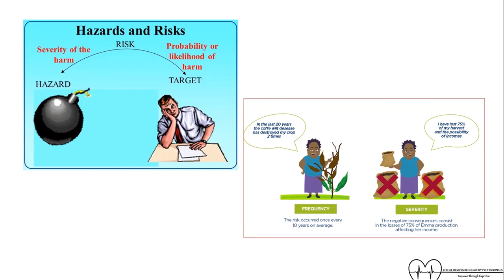I guess it's always, please think, first of all, start identifying, which I already touched upon, what is the hazard, what is the hazardous situation, meaning when it will happen. That is very, very important, and it's indirectly linked again to use, because you may identify in your FMEA that this failure mode is crazy, but it has hardly any risk to the patient because they don't use it this way. Then there is harm, and then you estimate, which is now the trickiest part, the probability of occurrence of this harm, then the severity of harm, and then multiply or combine them to estimate the risk. And below, what you see, green, blue, green, yellow, red, is a standard one which we get from ISO 14971 or as such.